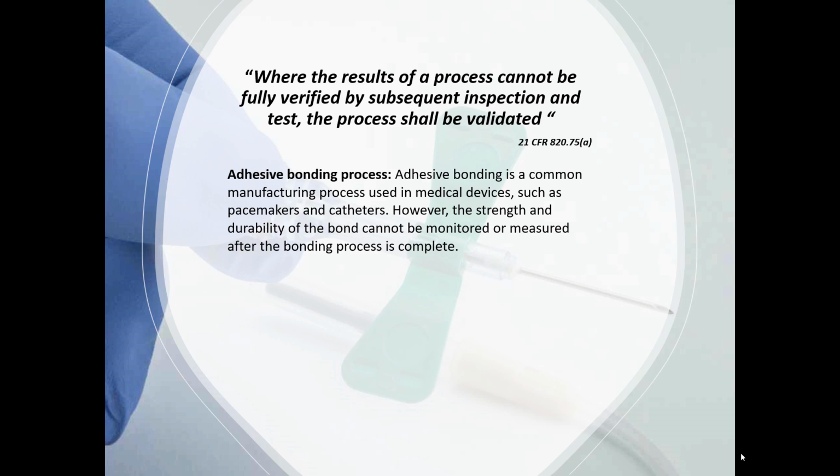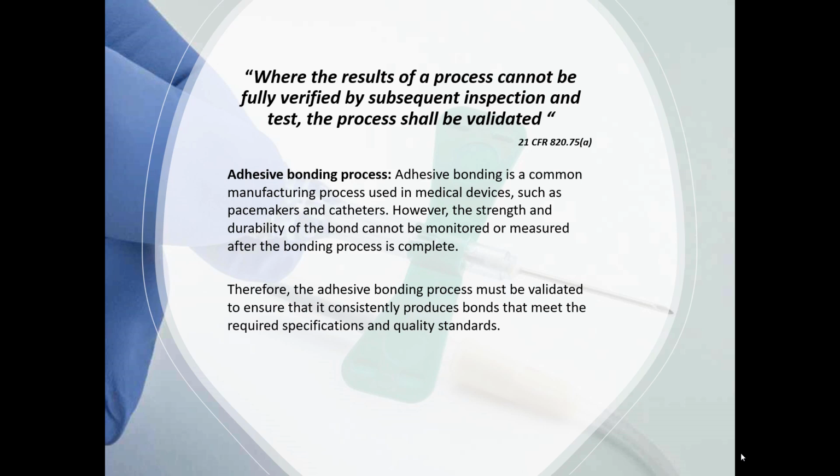But that cannot really be monitored or measured after the bonding process is complete, and therefore the adhesive bonding process must be validated to ensure that it consistently produces bonds that meet the required specifications of quality standards. So you have to do a validation of this process in order to be compliant with 21 CFR 820.75(a).